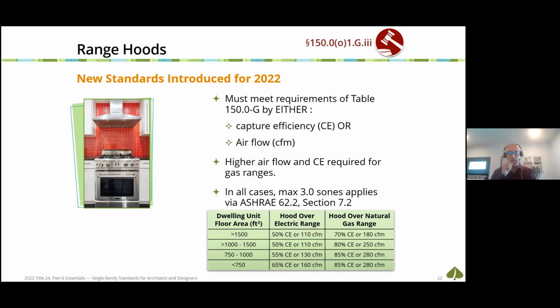You'll also notice something kind of confusing, maybe you wouldn't immediately grasp. There's higher CFM requirements when you have smaller dwellings, right? Normally we think of, okay, bigger house needs more ventilation, and that's true for IAQ. But for these spot sources, we need higher ventilation when those pollutants are concentrated in a smaller unit than when they're spread out, diluted over a larger building. So this is a good, for you energy consultants out there and architects, this requirement is good to highlight on your plan set to make sure it's not missed, to make sure adequate airflow is built into the kitchen range hood.